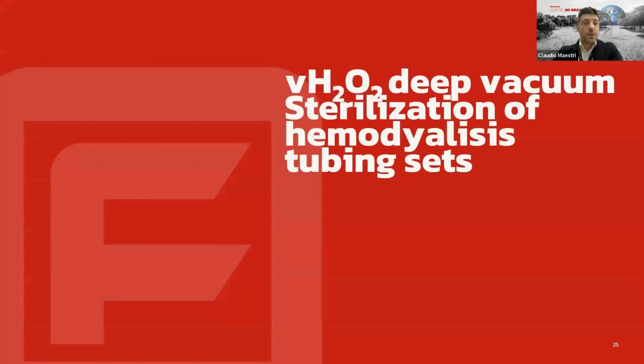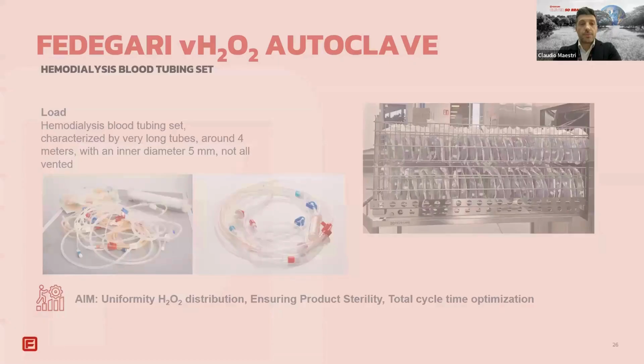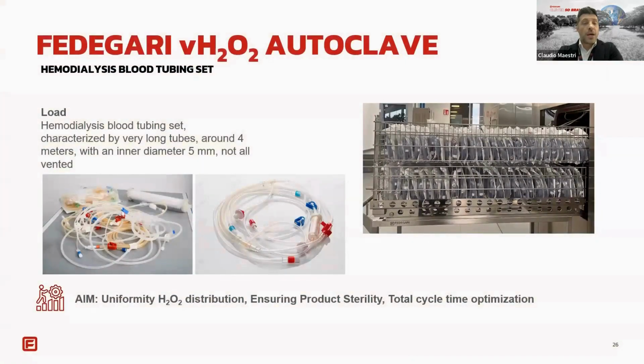Here we see the second case study that we want to share with you: the H2O2 deep vacuum sterilization of hemodialysis tubing sets. Hemodialysis tubing sets are extremely long and narrow, some up to 4 meters in length, with a 5 millimeter inner diameter, and not all vented. That makes the sterilization a huge challenge.